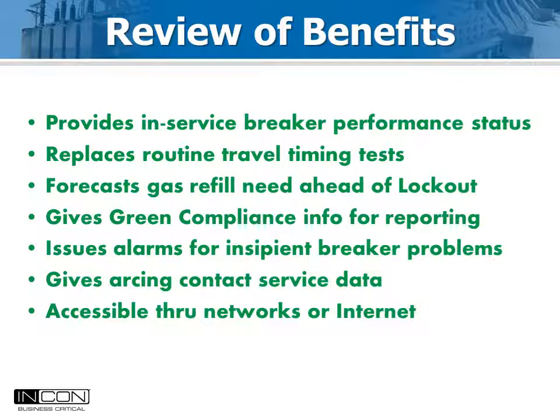The Optimizer 2 offers many benefits. It will totalize the lifetime use of SF6, making EPA reporting compliance easy. It will obviate the need for offline circuit breaker testing. First trip information will show any degradation in performance over the years. It also migrates the SF6 density integrity function toward the active and predictive smart grid realm.